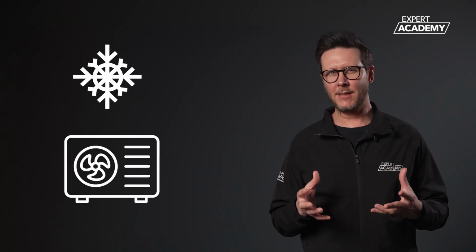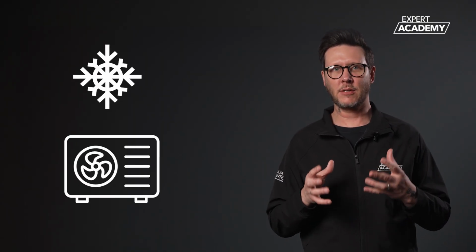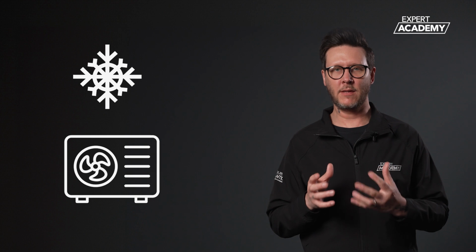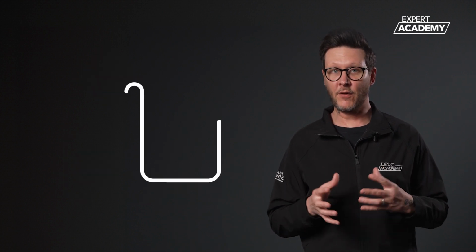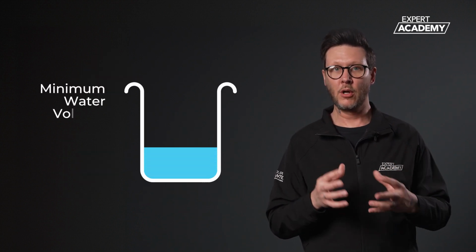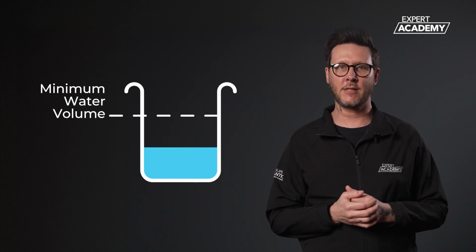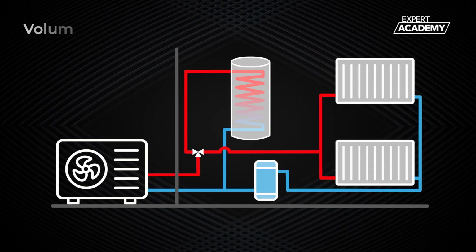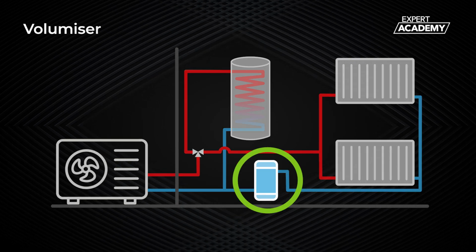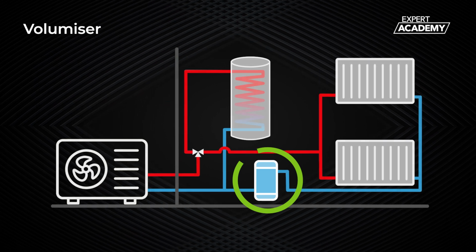As the heat pump completes its defrost cycle, it uses a small amount of energy from the water in the heating system. If the volume of system water was too low, not enough energy would be extracted to successfully complete the defrost cycle. To increase system volume, a volumizer can be installed on the heating return pipework.